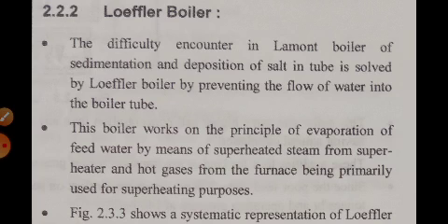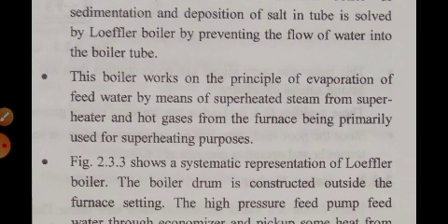The difficulty encountered in the Lamont boiler, of sedimentation and deposition of salt in the tube, is solved by the Loeffler boiler by preventing the flow of water into the boiler tube. That means the flow of water is not through the boiler tube. It works on the principle of evaporation of feed water by means of superheated steam from the superheater and hot gases from the furnace being primarily used for superheating.